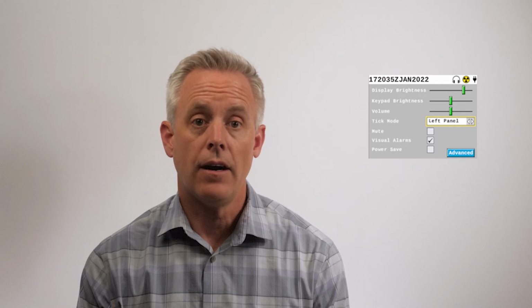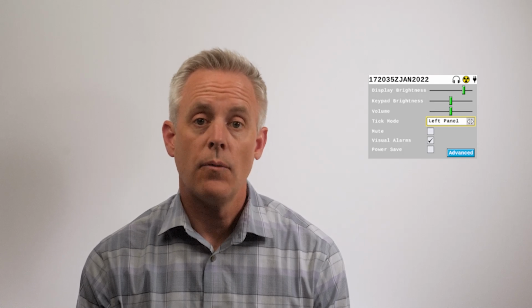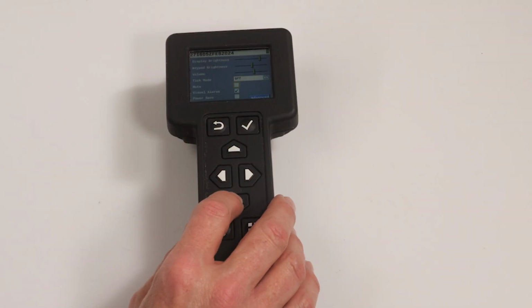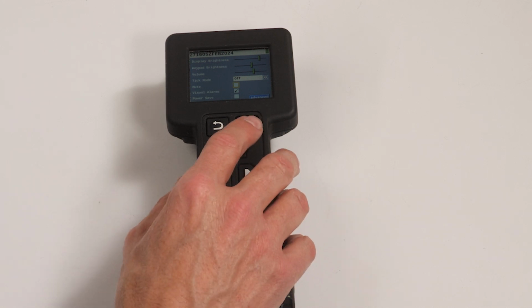When a probe is connected to the base unit, three options are presented: right panel, left panel, and off. Choosing the right panel or the left panel refers to the radiation readings on the home screen and will determine which readings are used for tick mode. If both the mute and tick mode settings are selected, mute cancels out tick mode. No ticks will sound. Press the down arrow key to highlight the mute function.